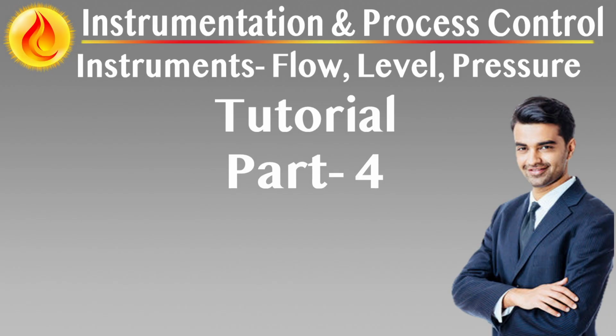Positive displacement meters for high-accuracy volumetric flow in custody transfer and viscous fluid applications. Positive displacement (PD) meters deliver direct, high-accuracy volumetric flow measurement by capturing discrete volumes of fluid between moving mechanical components. Each rotation or cycle of the internal mechanism corresponds to a known volume, making PD meters inherently linear, pulse-generating, and highly repeatable.